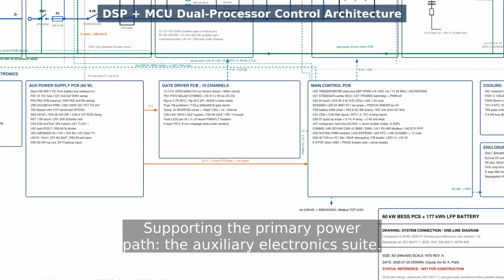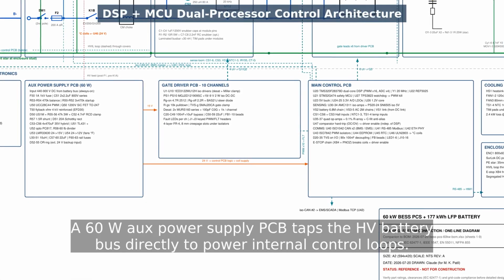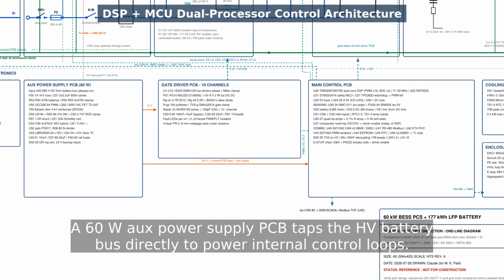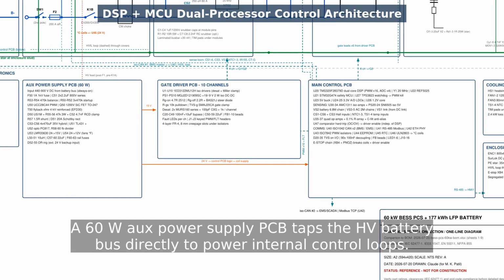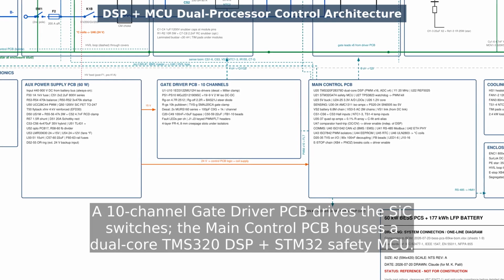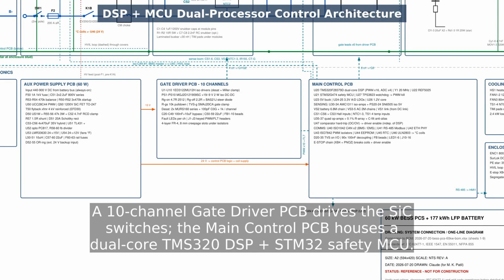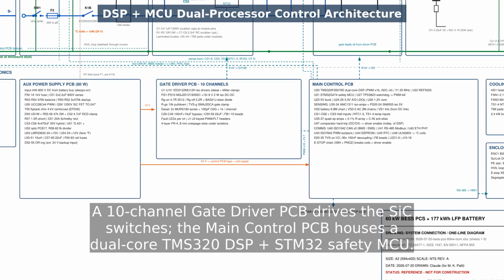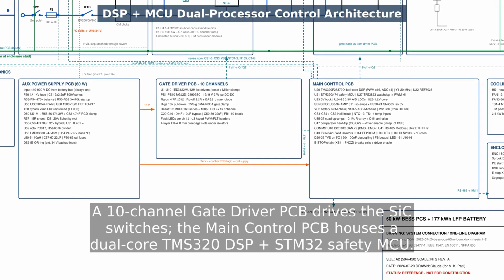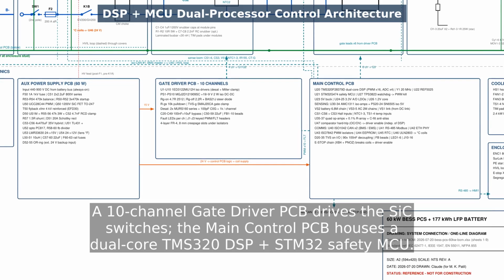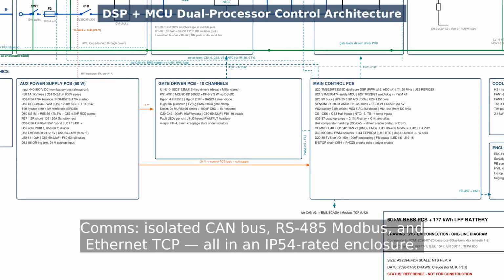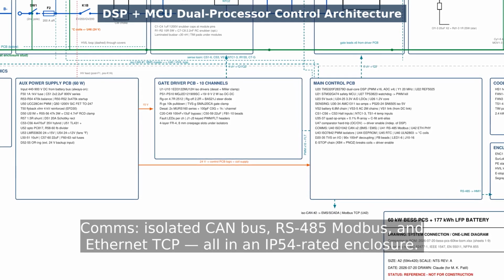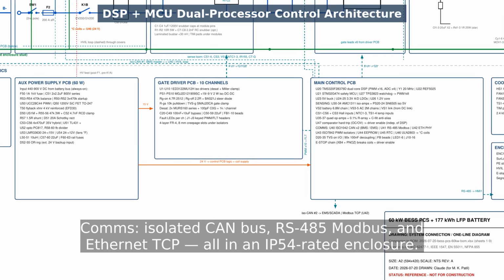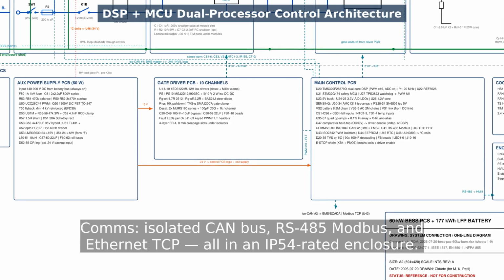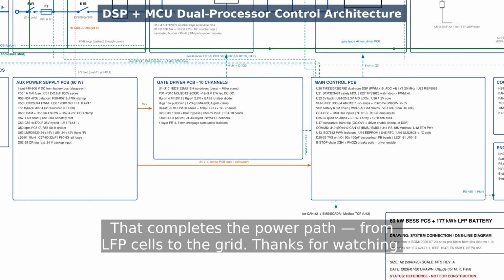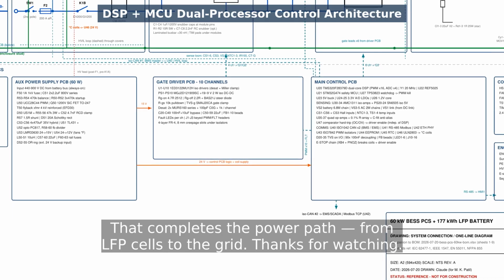Supporting the primary power path is the auxiliary electronics, with a 60 watt auxiliary power supply PCB tapping directly off the high voltage battery bus to power internal control loops. A dedicated 10-channel gate driver PCB drives the silicon carbide devices, while the main control PCB runs a dual-core TMS320 DSP and an STM32 safety processor. Communication is handled by isolated CAN bus, RS485 Modbus, and Ethernet TCP interfaces. All of this is housed in an IP54-rated enclosure, and it completes the power path from LFP cell all the way to the grid. Thanks for watching.